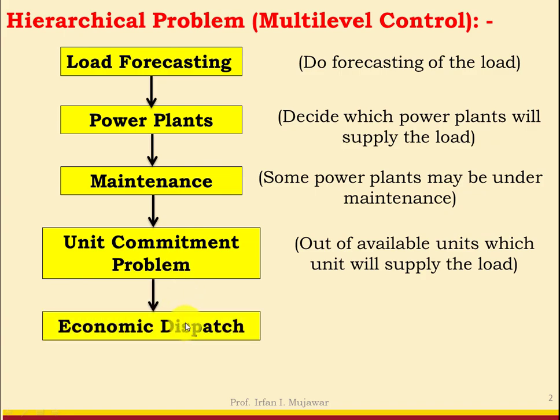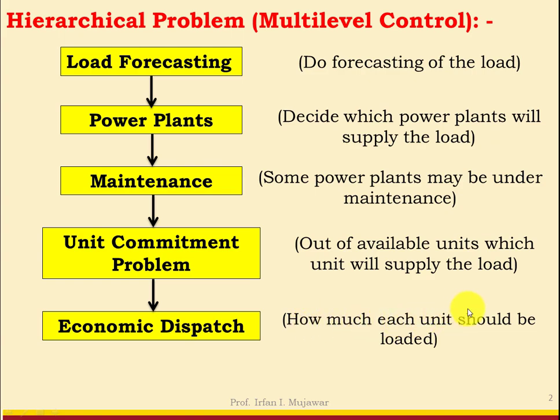Then next comes economic dispatch or economic load dispatch. In economic dispatch we are deciding how much each unit should be loaded. For example, suppose there is a unit of 100 MW rated capacity — should it be loaded to 80 MW, 70 MW, or 20 MW? Unit commitment is the selection of units that will cater to the load, whereas economic dispatch means how much each selected unit should be loaded.